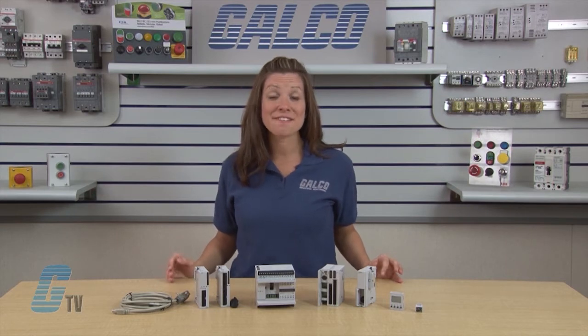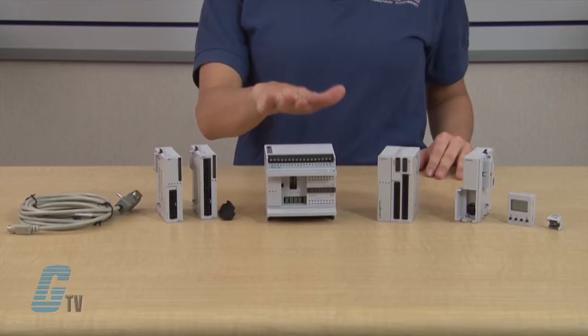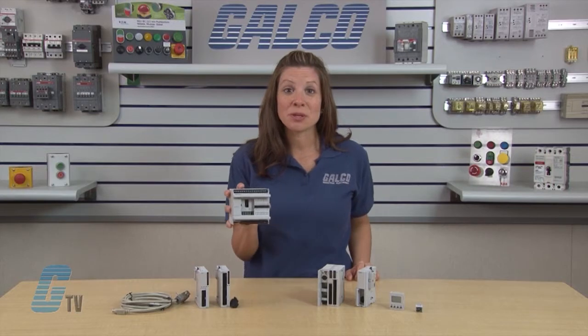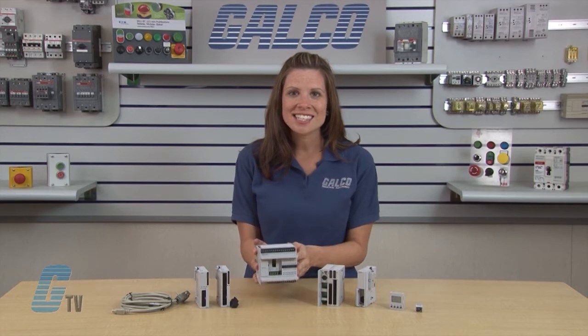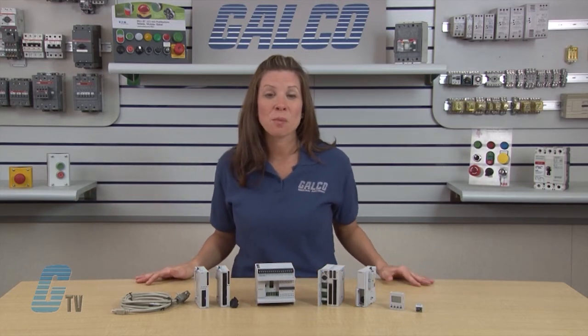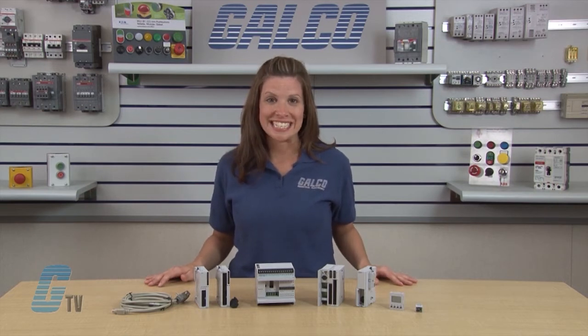IDEC MicroSmart is a family of micro-programmable logic controllers available in two styles of CPU modules: all-in-one and slim types. The all-in-one type CPU module has 10, 16, or 24 input-output terminals and is equipped with a built-in universal power supply to operate on 100 to 240 volts AC or 24 volts DC.